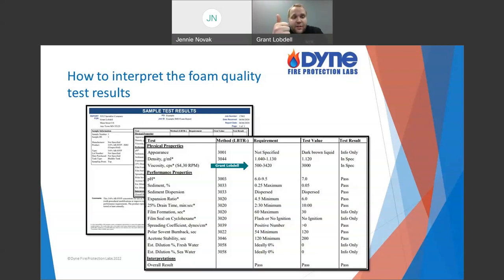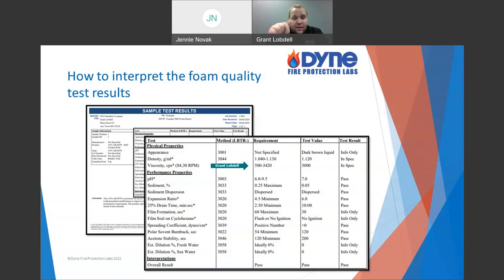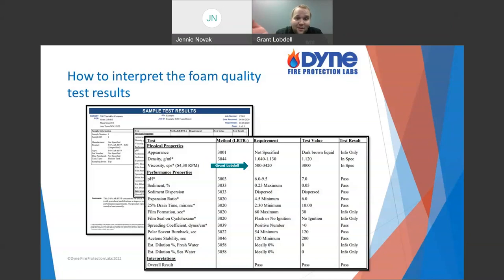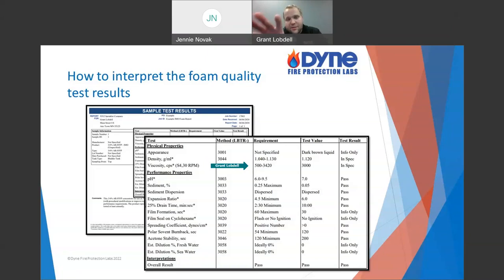Viscosity matters for flow testing as well — different thickness foams flow through equipment differently, which can impact proportioning. As a product, if a foam is designed to have 3,000 cP viscosity and it drops to 1,500, that means there's less polymer. Less polymer means less protection against alcohols. It's not that thicker is always better — it's all based on how the foam is designed. There are also low-viscosity products designed to have the same level of protection at maybe 1,000 or 2,000 cP. With all these results, you always go back to: how was it designed?